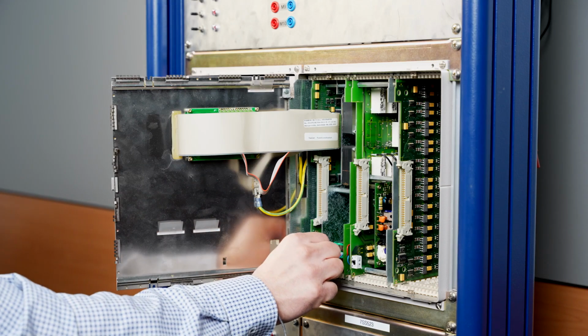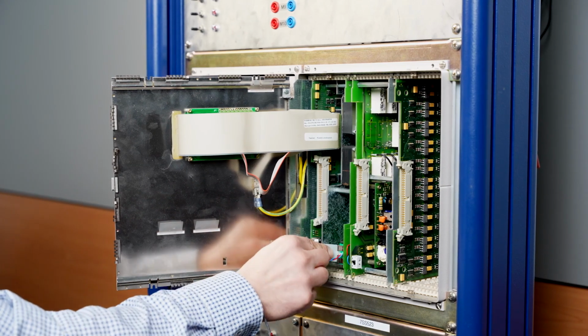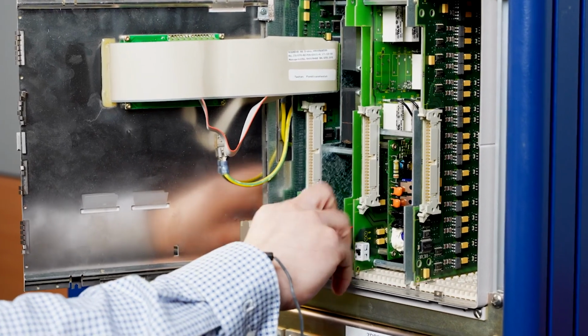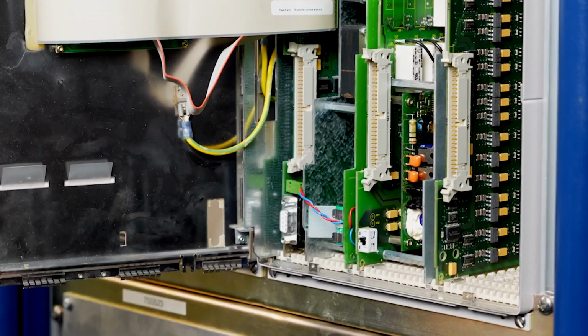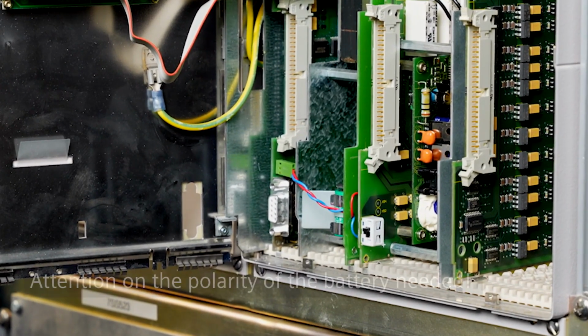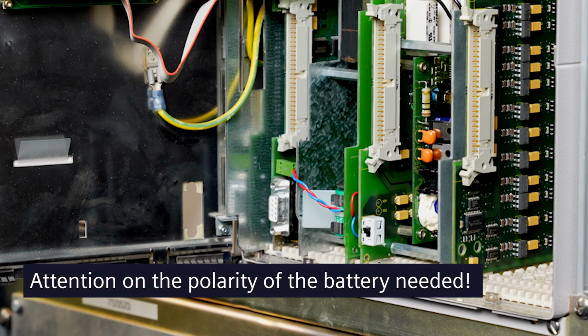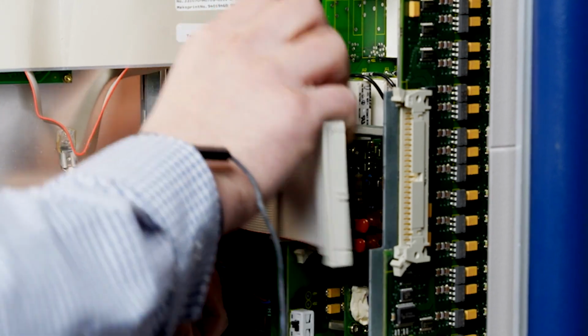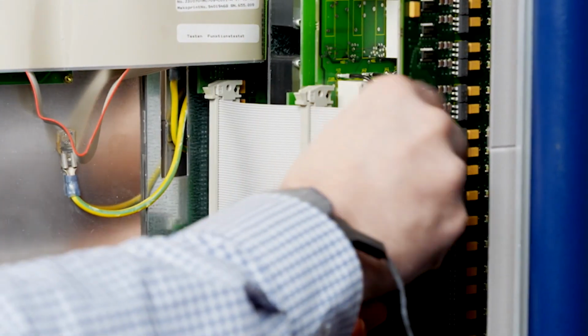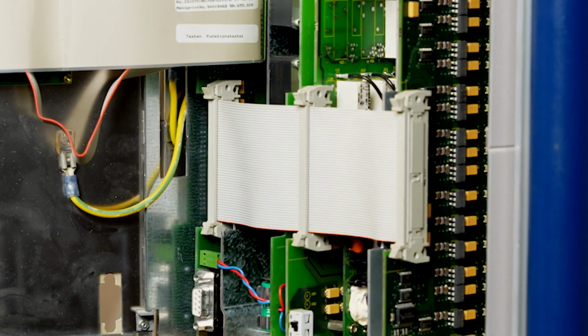To install the new battery, pull the cable tie with the tab over the battery cylinder and press the new battery into the holder on the assembly. Please pay attention to the polarity of the battery, this is marked on the circuit board. Then, carefully plug the ribbon cable back onto the pin headers. Please ensure that the connector plugs are not plugged in offset.